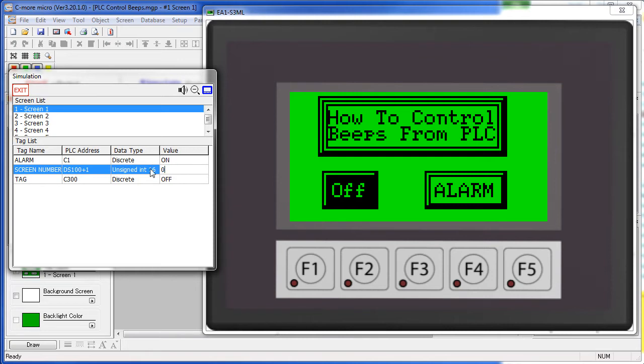Again, it's the transition from a 1 to a 0 that disables the tone. Simply writing a 0 to this tag when it's already a 0 won't silence the tone, so be careful about that.